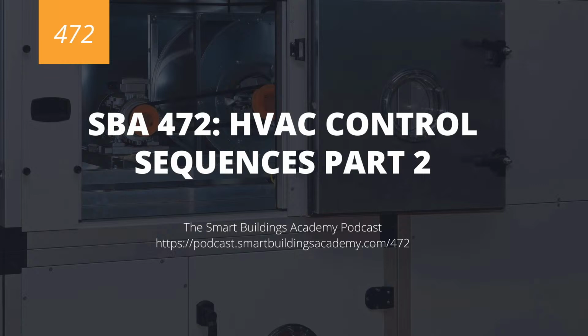Okay, so rooftop units. We talked about fans. We talked about our coils. We talked about our dampers. We talked about our set points. Now I'm going to read through some sequence language and just kind of help you understand some stuff. So, as I mentioned, we are going to go and control our rooftop unit based on achieving a set point, typically a room set point, and it's going to be an occupied and unoccupied, meaning occupied is occupied, unoccupied is unoccupied. I don't think I need to explain those.